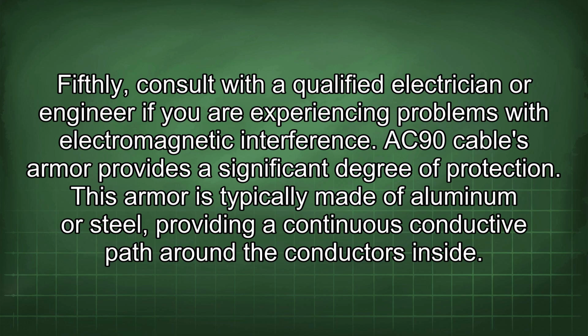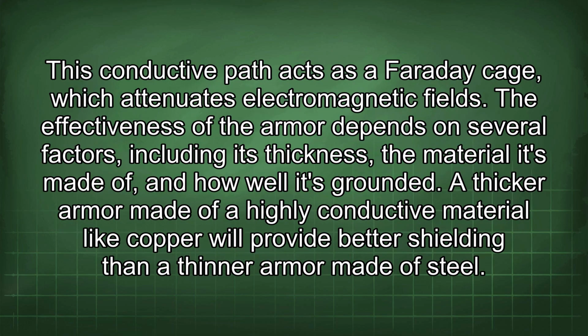AC90 cable's armor provides a significant degree of protection. This armor is typically made of aluminum or steel, providing a continuous conductive path around the conductors inside. This conductive path acts as a Faraday cage, which attenuates electromagnetic fields.